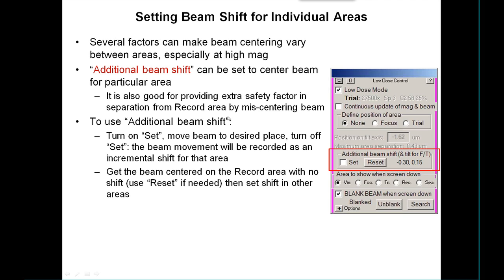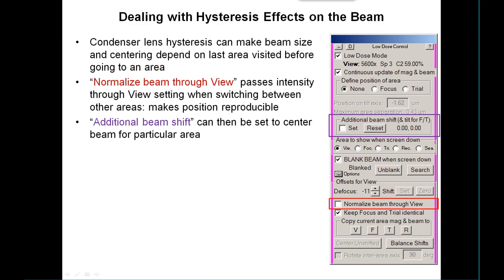To use the additional beam shift, you turn on the set button, move the beam around to where it's centered in the area you want, then turn off the set button. All those movements get recorded as the extra amount that's supposed to happen when it goes to that area. The practice is to get the beam centered in the record area with no shift — you might have to use reset if somehow you've got a shift in there — then shift to the other areas and set the shifts there. You might still find that centering isn't consistent, possibly because beam size or beam centering differs depending on the last area visited before going to a particular area.